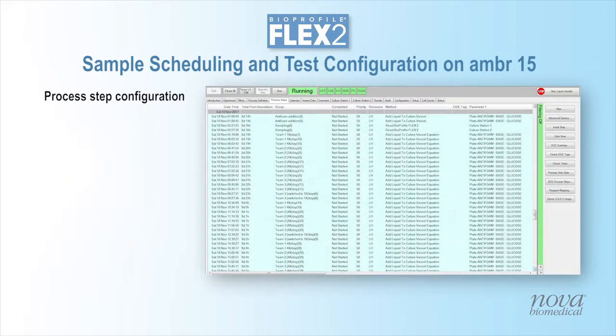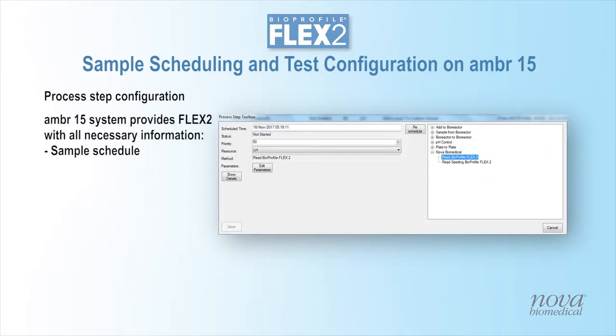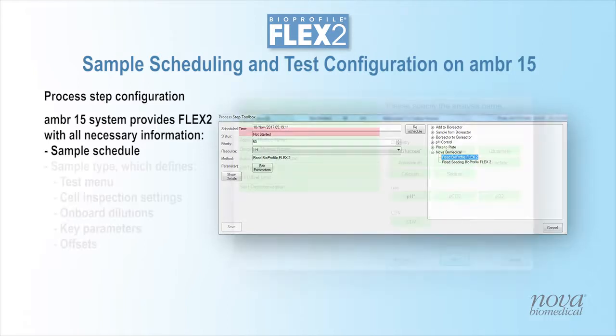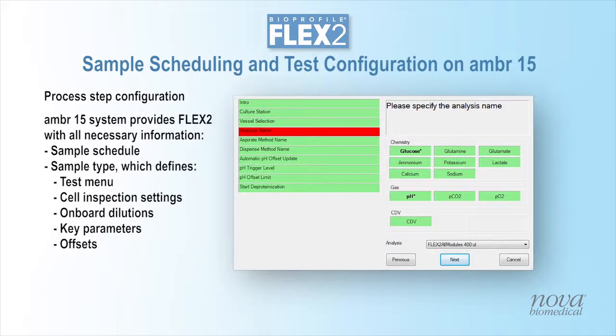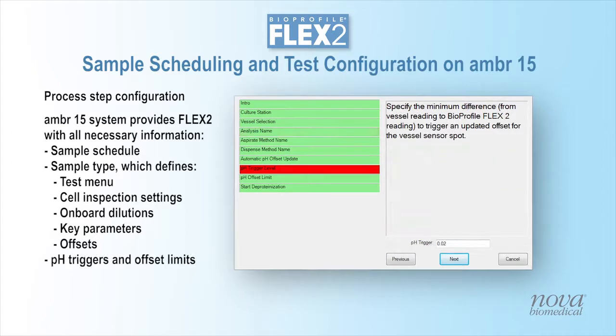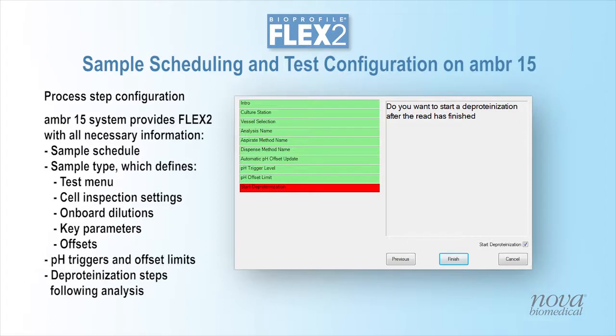Sample scheduling and test configuration are performed via the ambr 15 user interface. New process steps can be created or existing process steps modified to schedule sampling of each micro-bioreactor followed by analysis by the Flex2. Process step configuration includes sample scheduling, selection of the sample type which defines the test menu, cell inspection settings, onboard dilutions, key parameters and parameter offsets, as well as pH trigger points and offset limits, and deproteinization steps following analysis.